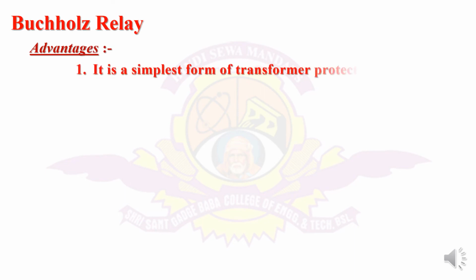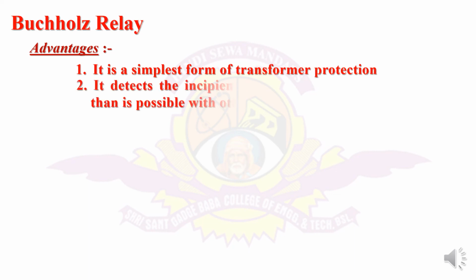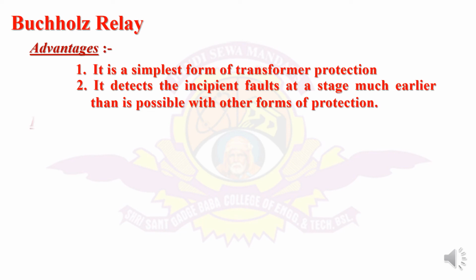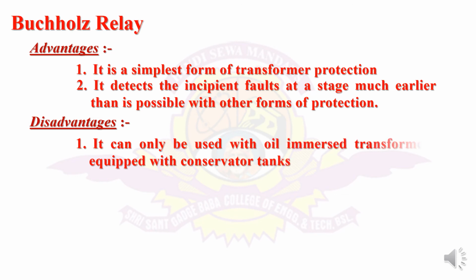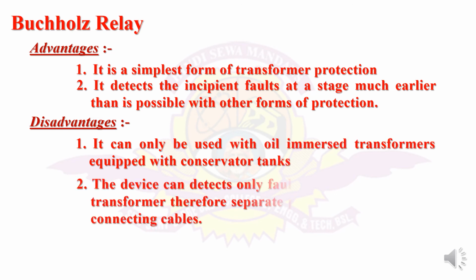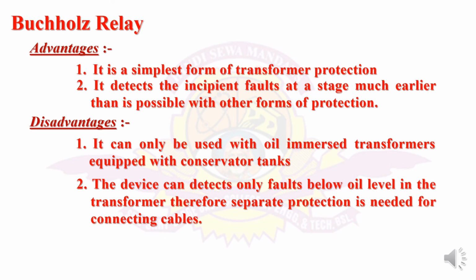Now the advantages and disadvantages of the Buchholz relay. Two advantages are there. First advantage is that it is the simplest form of transformer protection, and second, it detects the incipient fault at a much earlier stage than is possible with other forms of protection. And the disadvantages are, it can be used only in case of oil immersed transformers which are equipped with a conservator tank. If a conservator tank is not there, we can't apply the Buchholz relay. As well as, this device detects only the fault below the oil level. Faults above the oil level can't be detected by using the Buchholz relay, and for that purpose, for protecting the connecting cables, we have to apply another level of protection. Thank you.